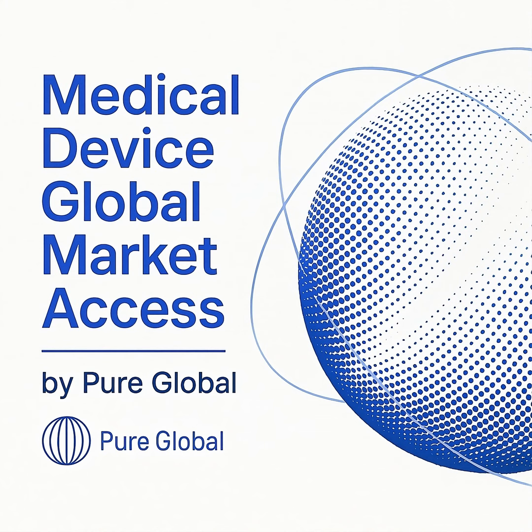The process does not end at market launch. Manufacturers must establish a post-market clinical follow-up, or PMCF, plan. PMCF is a proactive process of collecting and evaluating clinical data from the use of a device that has already been placed on the market. This confirms the long-term safety and performance, identifies previously unknown side effects, and ensures the benefit-risk profile remains acceptable. The findings from PMCF are used to update the clinical evaluation report and are a key input into the device's vigilance and risk management systems.